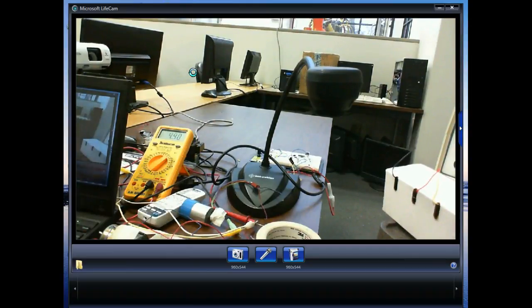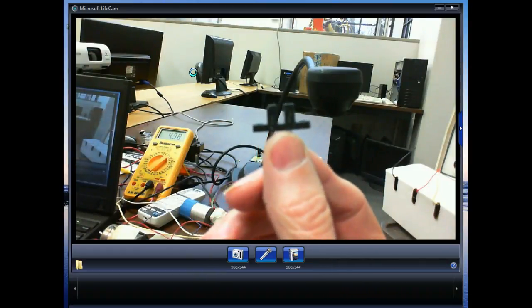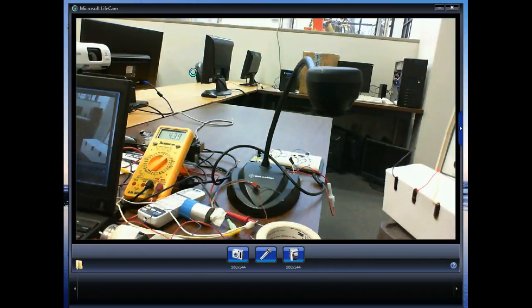An encoder is nothing but a wheel that has a bunch of holes. That's all it is. And then we have something that we refer to as an optical interrupter. This is a through-the-beam sensor. It's called an optical interrupter because what we want to sense breaks the beam. Here's the emitter, here's the detector. You put something in there that breaks it, we know it's present.